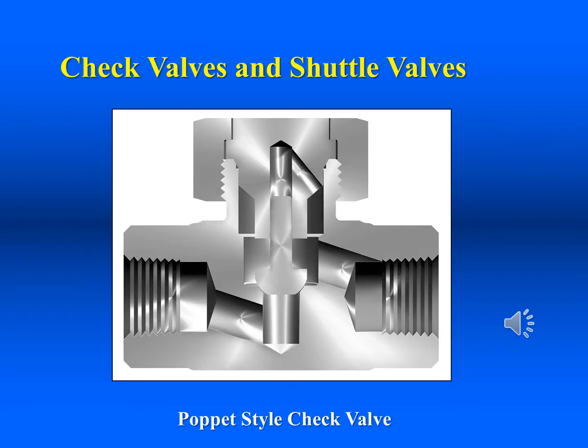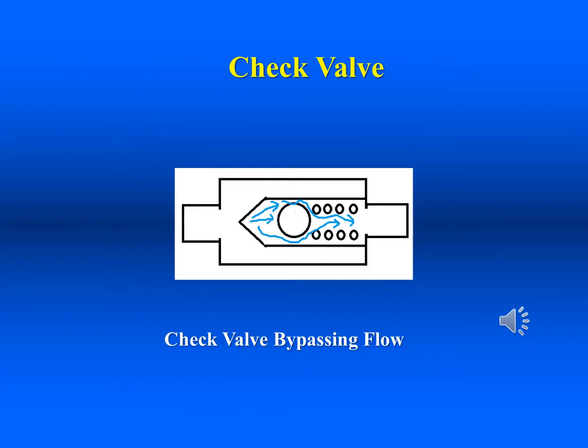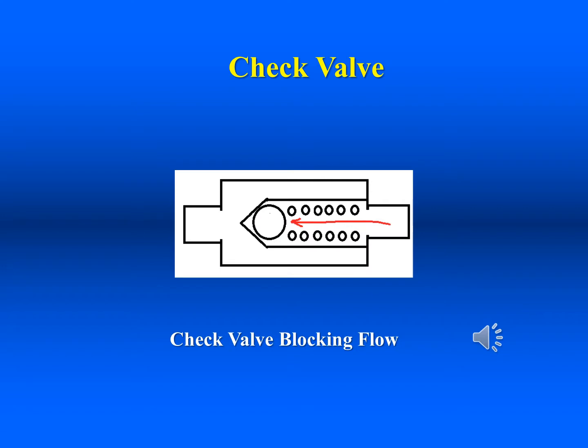Check valves block fluid flow in one direction, much like a diode blocks electrical flow in one direction. Their primary function is to provide a path of free flow around a device when the function of that device is only needed in a single direction. The most common movable members used in check valves are steel balls and poppets. In free flow, the fluid pushes the movable member against a light spring and flows around it. In blocked flow, the fluid moves in the direction which forces the movable member against a seat, causing it to choke off fluid movement.